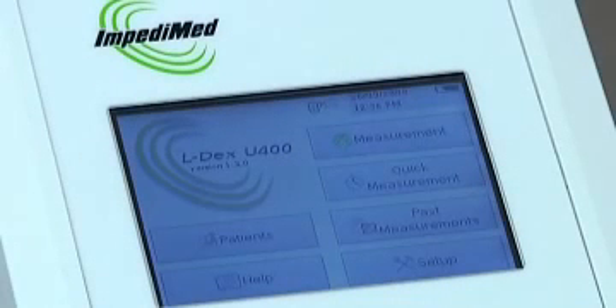Taking an L-Dex reading on ImpediMed's U400 is easy. There are 3 ways to take a measurement, and we will go over the most common use in this video. Please refer to the instructions for use for other measurement options. The subject should arrive for testing in a normally hydrated state. Stockings should not be worn, as you will need to place a gel electrode on the skin of one foot. Have the patient remove the right shoe and sock. Any jewelry between the wrist and the ankle should also be removed. Any metallic objects such as a cell phone should be removed. Rings and earrings need not be removed as they will be outside the field of measurement.